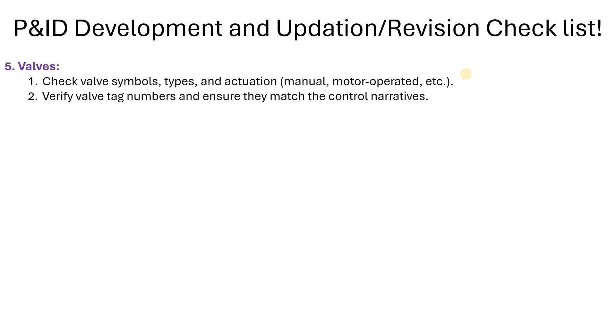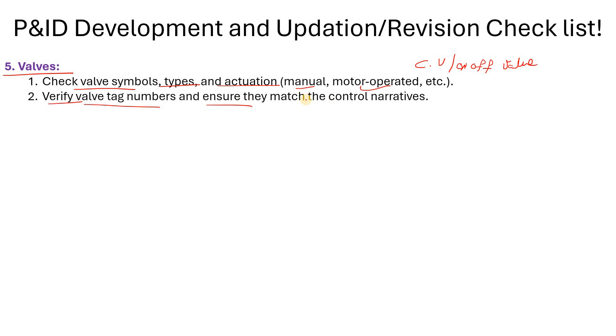Now, valves — this part is very important to consider. Please check the valve symbol, the type of valve, and the actuation — whether you are using a manual valve, motor-operated valve, control valve, or on/off valve. You must check that. Then verify your valve tag number and ensure they match the control narratives.